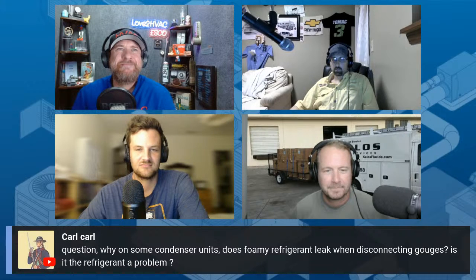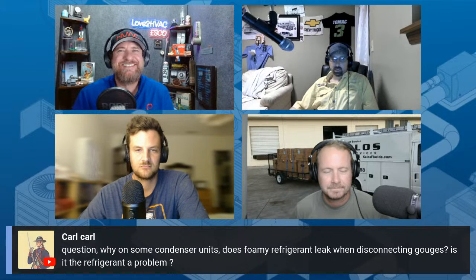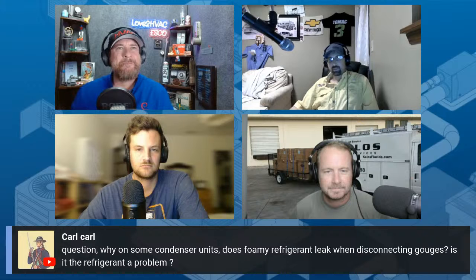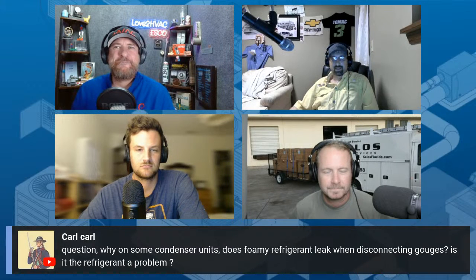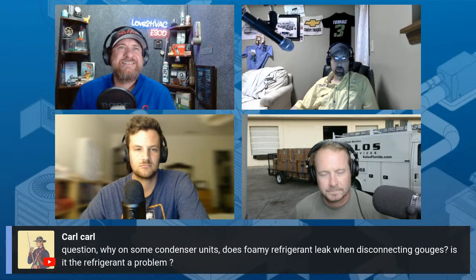No, it's just a dynamic system. Say you replace a capacitor on a system that's been sitting off, humming, with oil stagnant in the lines—then you fire it off, put your gauge on it, and it shoots a little slug into your gauge. It's all about what's going on with that system. Obviously, systems that are low on charge, when you add charge, the oil starts coming back, and you'll find that a lot more.